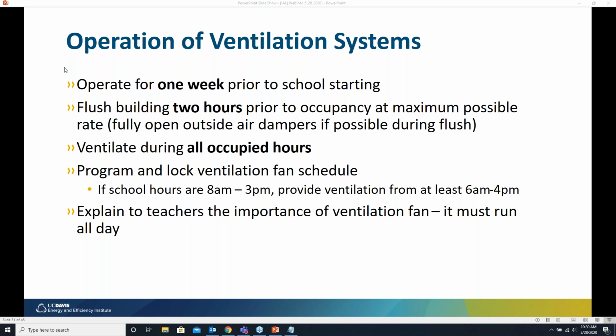So, operation of ventilation systems. It's recommended to operate your systems 1 week prior to school starting. There are 2 reasons for this. The first is to make sure that everything is functioning correctly. The second is to remove indoor pollutants that have built up over the course of these extended shutdowns. Also recommended is to flush the building 2 hours prior to occupancy every day at the maximum possible rate. Pre-COVID-19, this recommendation was 1 hour a day, so this has doubled. Ventilate during all occupied hours, that's always required. And then program and lock your fan schedule to ensure that teachers can't turn it off during the day, to make sure the ventilation system is working all day.